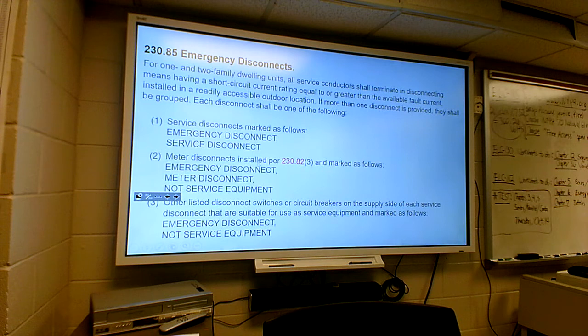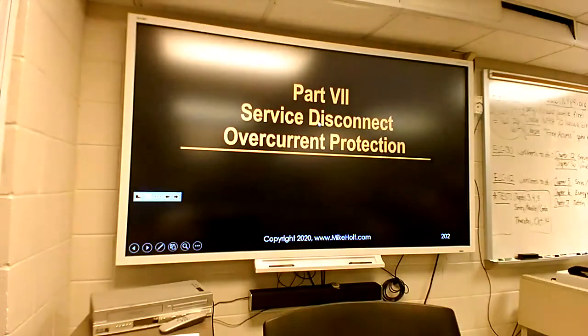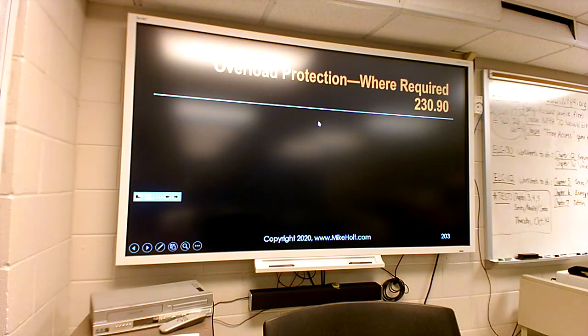For one and two family dwelling units, all your service conductors shall terminate in a disconnecting means having a short circuit current rating equal to or greater than the available fault current, installed in a readily accessible outdoor location. If more than one disconnect is provided, they shall be grouped. Part 7, overcurrent protection, where required.